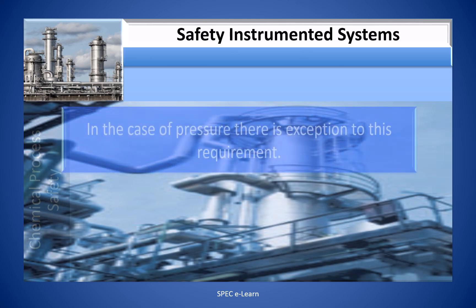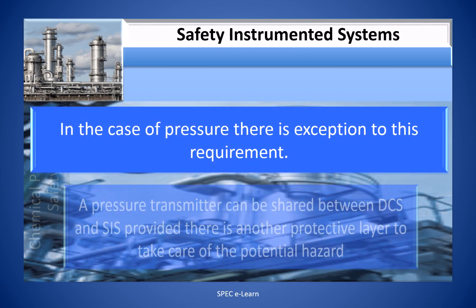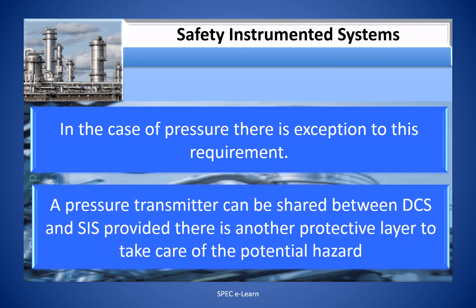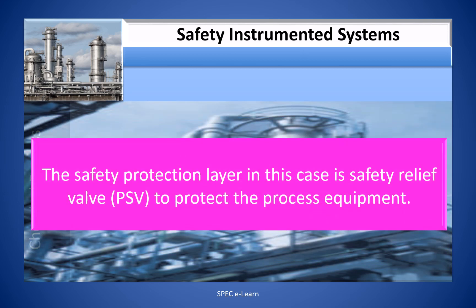In the case of pressure, there is an exception to this requirement. A pressure transmitter can be shared between DCS and SIS provided there is another protective layer to take care of the potential hazard. The safety protection layer in this case is a safety relief valve or PSV to protect the process equipment.